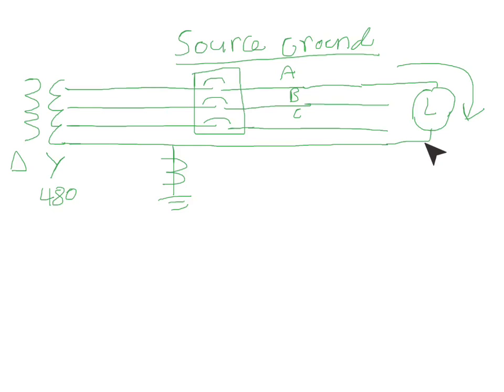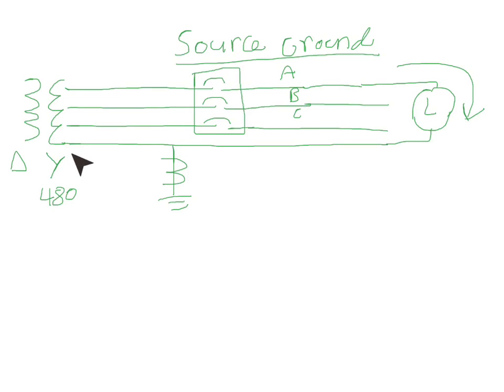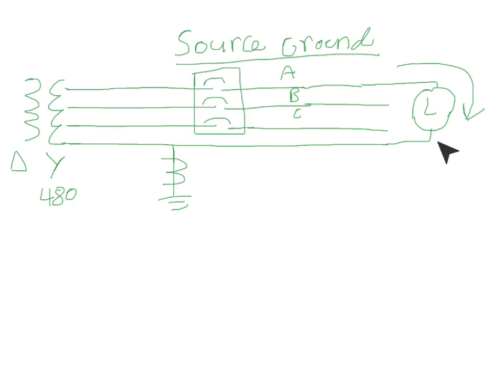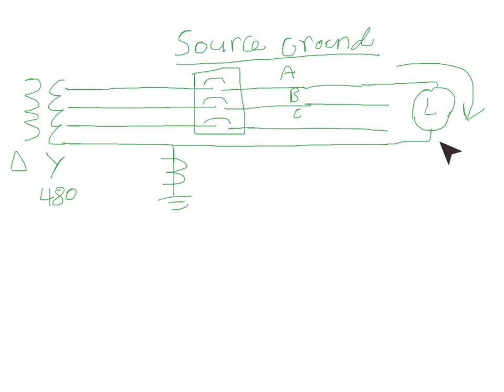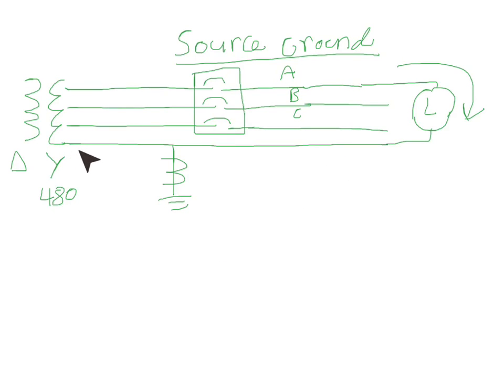Now as mentioned before, it could be XO on the transformer, which is the neutral, could be a jumper to the frame. And you're going to want to make sure that if that's how they installed it and that's the case, then there's not some other ground bonding over on this side of the system. You can actually take those grounding straps off on XO, and that's what I recommend you do.